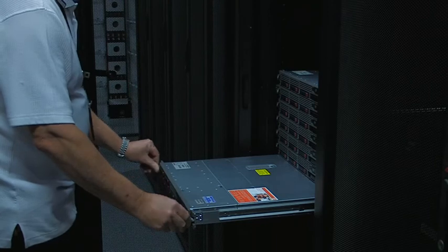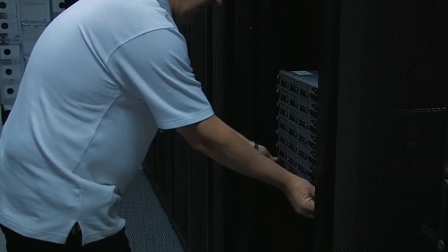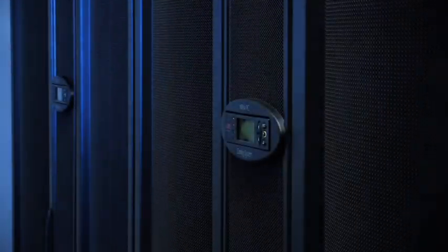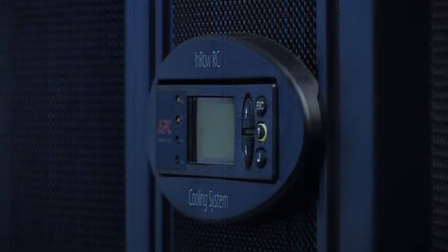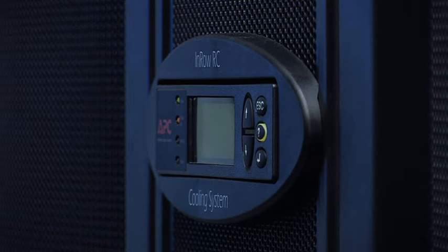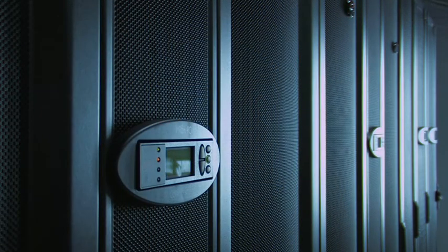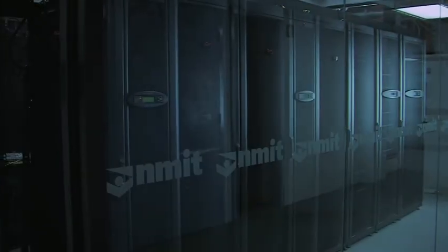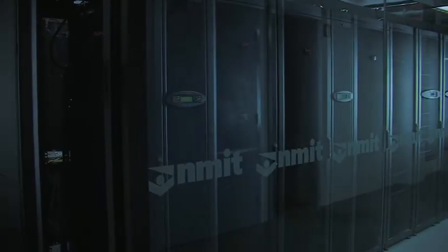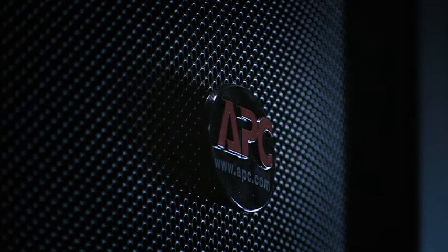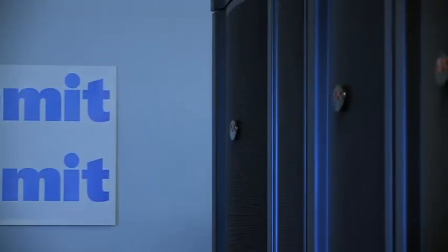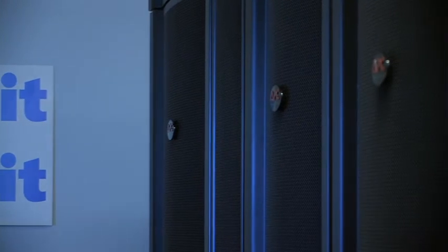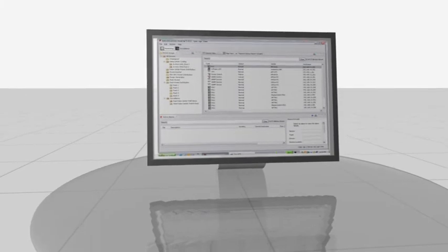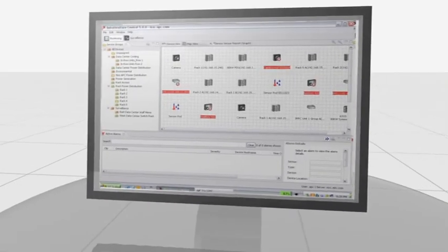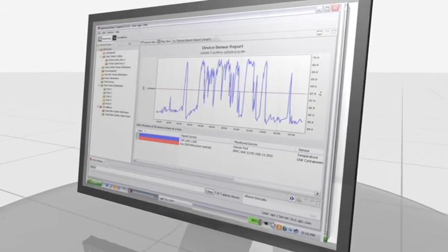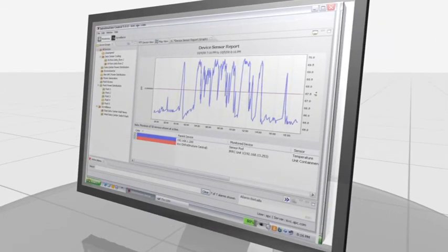The management console reports to a central application which collects information on power consumption, environmental parameters, cooling distribution, and the status of components for trending and periodical analysis. Overall, the system is a well-integrated and flexible solution for the data centre with a life cycle of more than 10 years, which is substantial in rapidly changing IT environments. The reading of the efficiency of the data centre, PUE and DCIE, is a very simple and straightforward process that can be scheduled at any time.